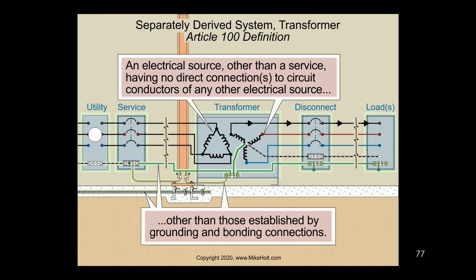Let's read the actual definition: a separately derived system is an electrical source — which is the secondary winding — other than the service, having no direct connection. None of the secondary conductors are connected to the primary conductors — no direct connection to the circuit conductors of any other source, other than those established by grounding and bonding.